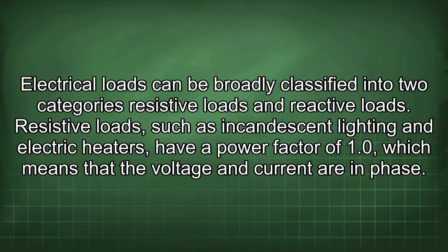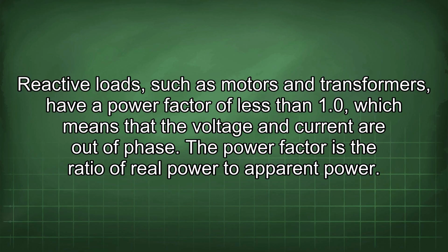It's also crucial to understand the different types of electrical loads and how they affect conductor sizing. Electrical loads can be broadly classified into two categories: resistive loads and reactive loads. Resistive loads, such as incandescent lighting and electric heaters, have a power factor of 1.0, which means that the voltage and current are in phase. Reactive loads, such as motors and transformers, have a power factor of less than 1.0, which means that the voltage and current are out of phase. The power factor is the ratio of real power to apparent power.